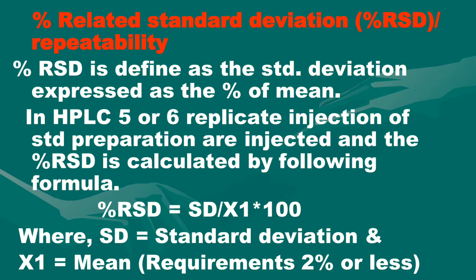Number one is percentage RSD. Percentage RSD is defined as the standard deviation expressed as a percentage of the mean. In HPLC, five or six replicate injections of standard preparation are injected and the percentage RSD is calculated by the following formula: Percentage RSD = (SD / X̄) × 100, where SD is standard deviation and X̄ is the mean. The percentage RSD should be two or less.